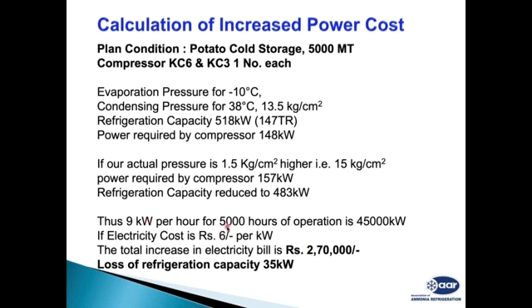Potato cold storage normally runs 9 to 10 months in India, so I've considered only 5,000 hours of operation. At 6 rupees, it will come to 270,000 Indian rupees. Also, this will have a refrigeration capacity loss of 35 kilowatt. To compensate this 35 kilowatt, you may have to run an additional compressor, or compromise on the refrigeration capacity of the system. If you add this 35 kilowatt of refrigeration capacity, then the cost will go up to almost 400,000 Indian rupees, or 4 lakh.